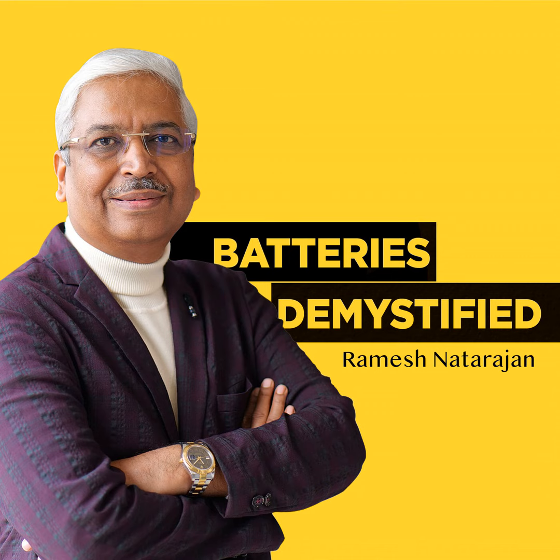Next point to be considered is as regards ventilation. This is very, very important because when a lead acid battery is being charged, both oxygen and hydrogen are evolved. A hydrogen concentration of more than 4% is very unsafe and can lead to an explosion or fire, especially if there is any sparking or a person entering a battery room either with a cigarette or something in his hand, which can lead to a fire. And this ventilation becomes very important because we do not want any mishap to happen in a battery room which can be of dangerous consequences.